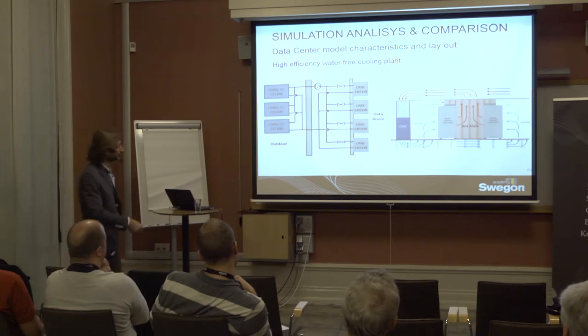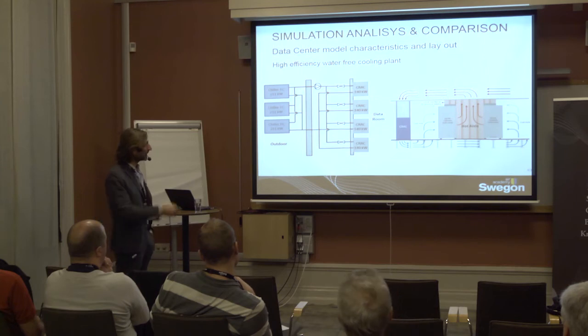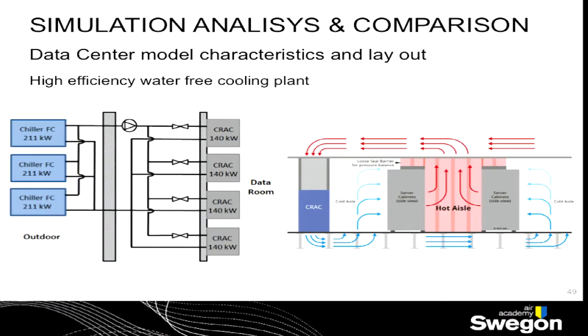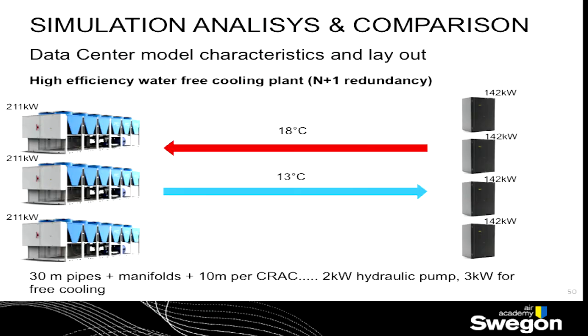This is a perimeter cooling based on CRAC units with a hot air containment, and the cold air is delivered into the building through a false floor. We have got a redundancy. As my colleagues underlined before, you always have to consider the redundancy of a system in a data center. Here we consider an N+1 redundancy. What does it mean? It means that if you make the sum of the total power that the chillers can deliver, you obtain 1.5 times the maximum cooling power requested by the data center. If you remember, you have got 400 kW, and here we have got more than 600 kW available.